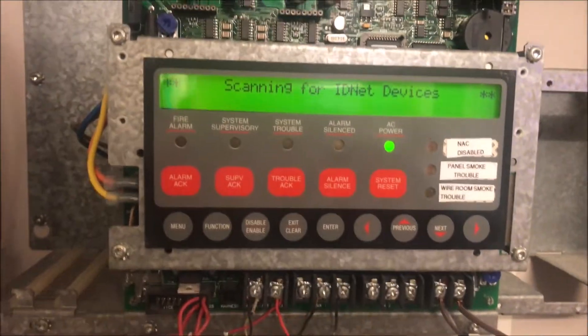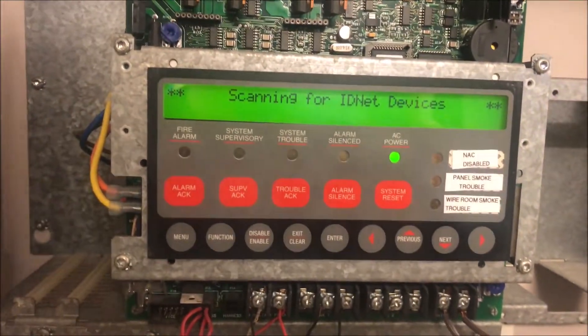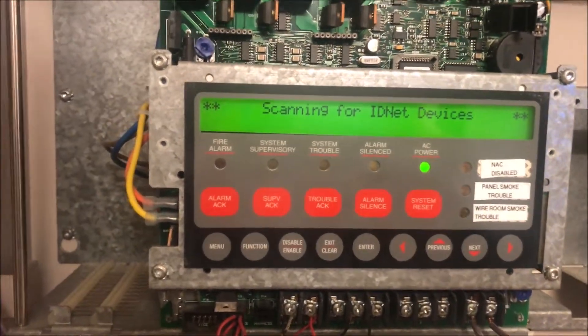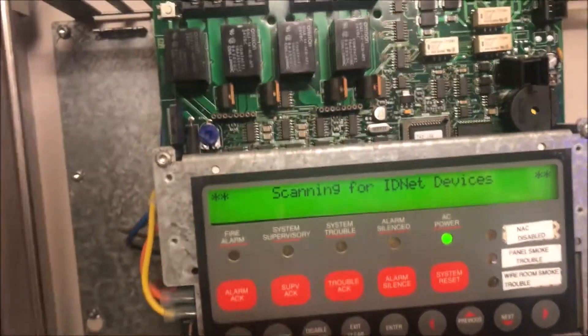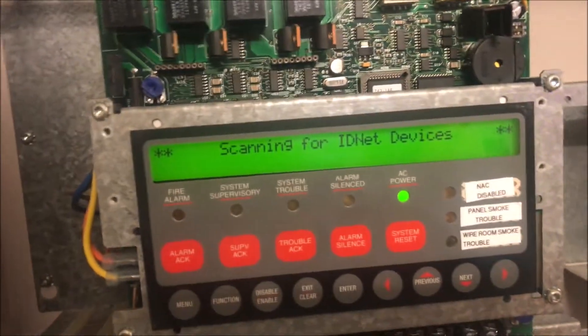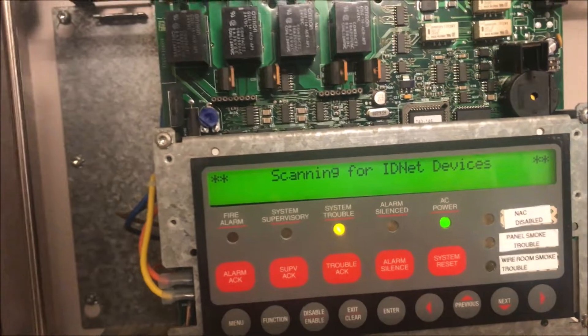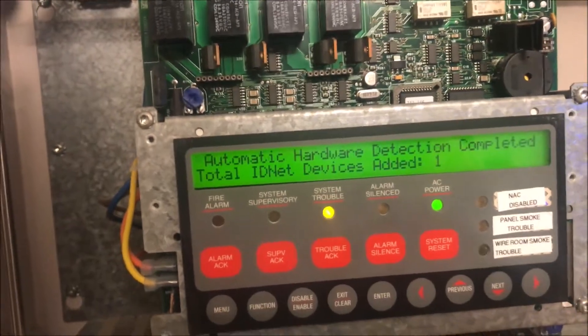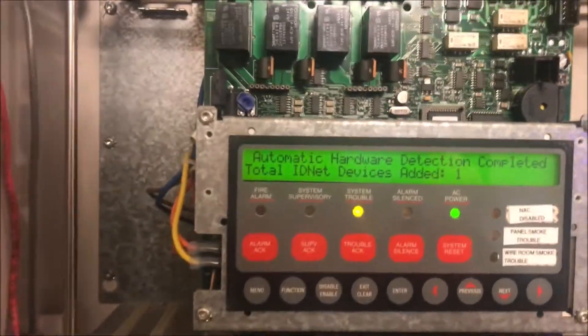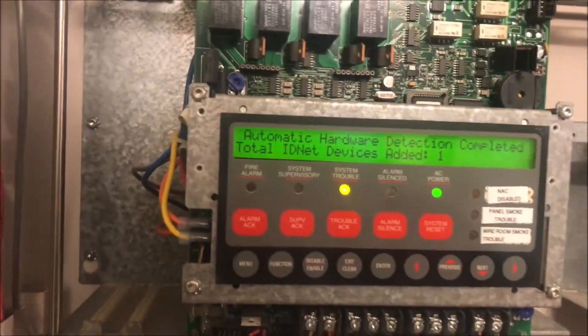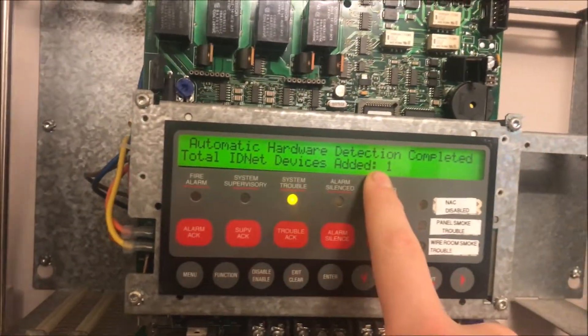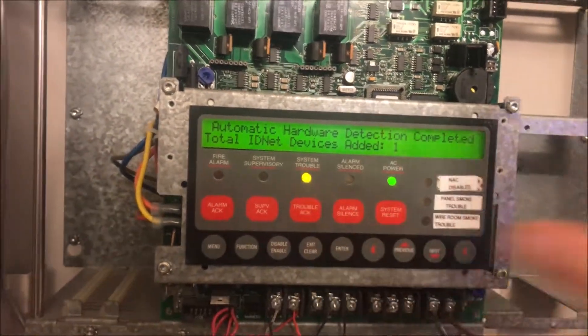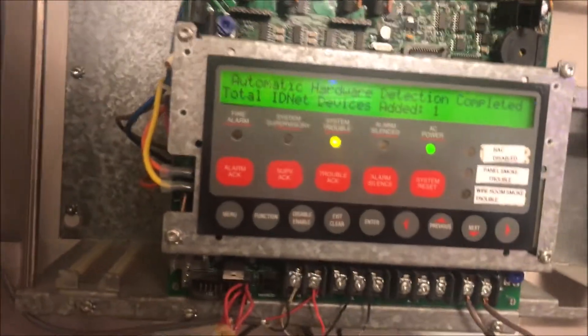It's comparing every device that it hears back because the device is sending back different frequencies. It's listening for every frequency and checking to see if it has that already in its list of known points. It says total IDnet devices added one. This is great if you're setting up a panel for the first time - you have 250 points, you just hit enter and it puts them all in.